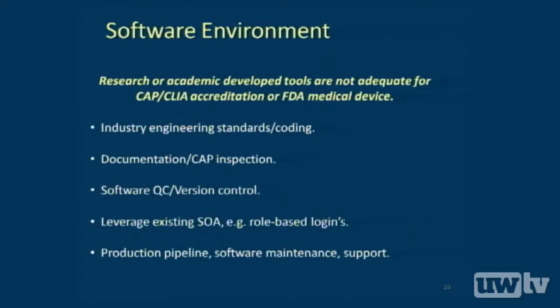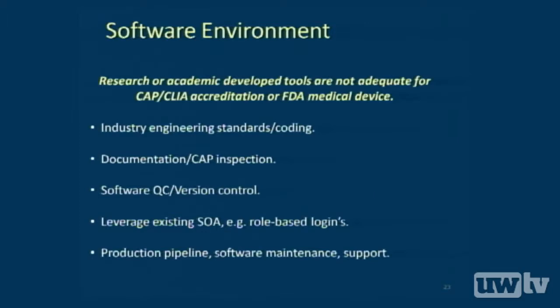One last note about the software environment. Many of us are familiar with open-source or academic settings — fluid, dynamic, and collaborative. But that environment is typically not adequate for CLIA accreditation or FDA medical device standards, where you're thinking in terms of industry coding standards, code commenting, CAP inspections, documentation, software control, and version control. If you want to leverage an existing service-oriented architecture like role-based logins already at play within your institution, you shouldn't have to rebuild that. In a production setting, software maintenance, help desk, and support make this environment very different from a research environment.